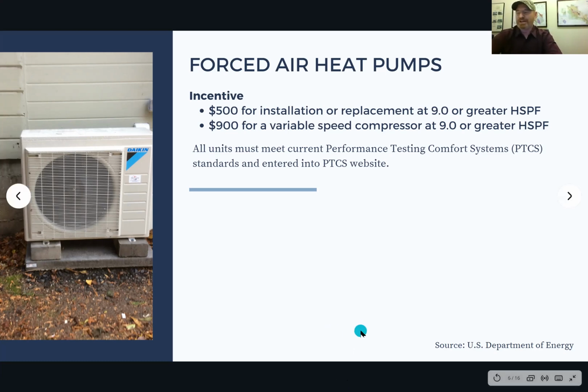And last but not least, when you are with a heat pump in the heat mode, make sure that the unit is in just heat, because all heat pumps will have some type of auxiliary heater. Make sure it's just in heat and not auxiliary or emergency heat, as that means it's running on the strip heat and it's going to be very expensive. So make sure that it's on heat.